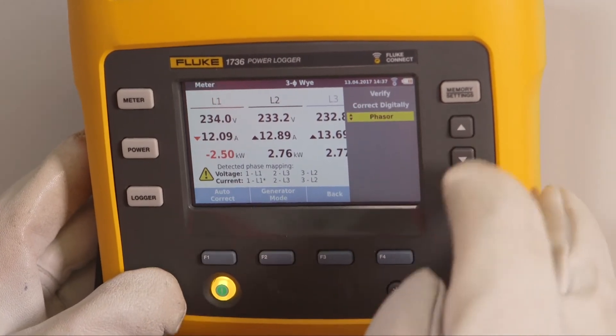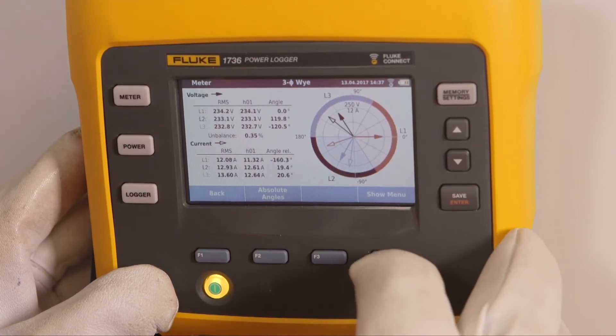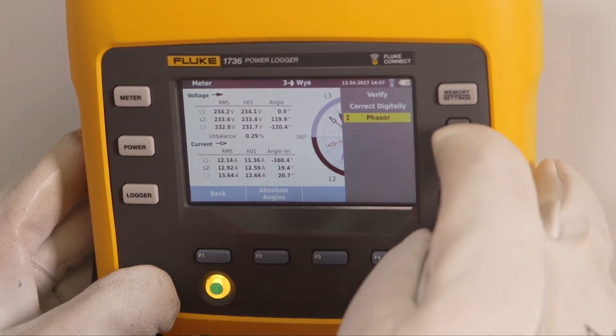He double checks the connections. The phasor diagram shows that one current is in counter phase. This needs to be corrected.